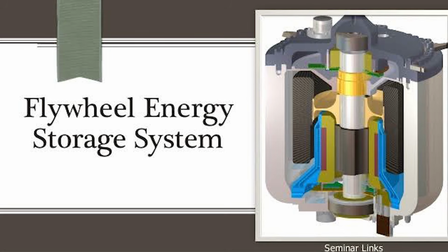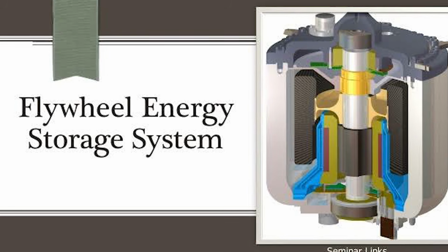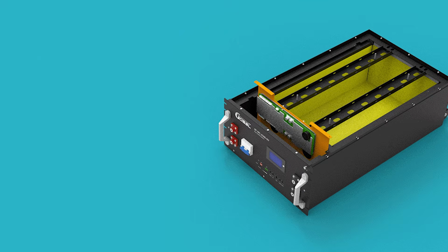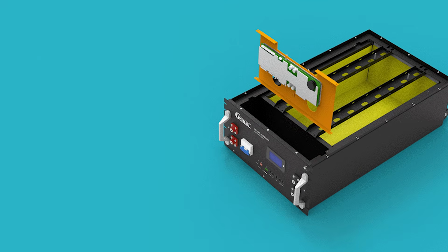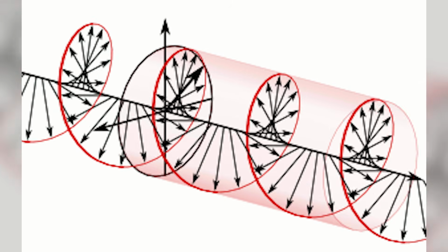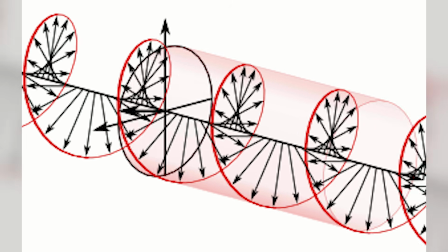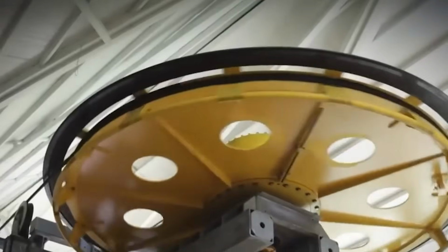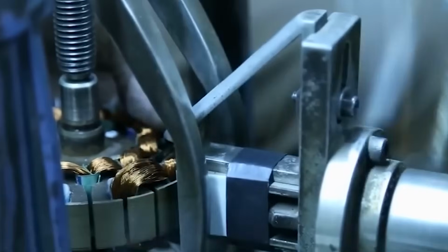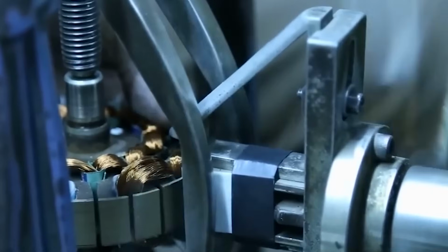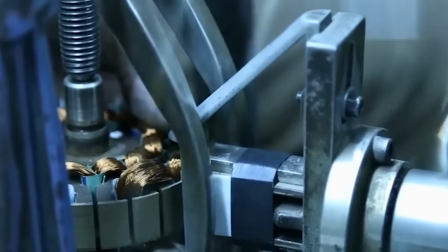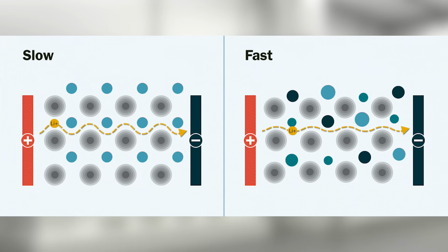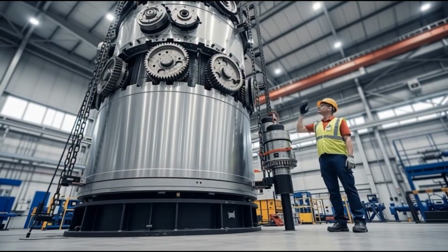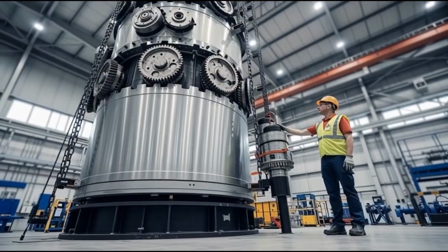Second, flywheel systems have higher standby losses than lithium. A fully charged lithium battery sitting idle loses less than 2% per month. A flywheel in a vacuum with magnetic bearings still experiences small rotational friction losses that are higher than lithium's static self-discharge. For daily cycling applications, where you charge each morning and discharge each evening, this difference is negligible. But if you want to charge a system and leave it untouched for two weeks, lithium retains more energy. Flywheels are optimized for frequent cycling, not long-duration static storage.